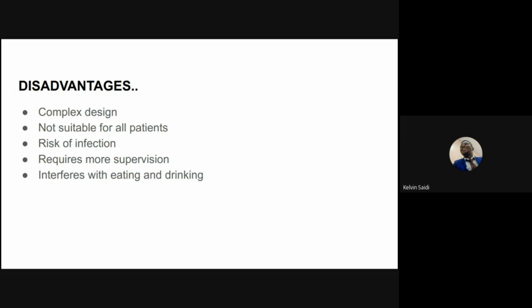It is also important to note that they do require more supervision. So the flow rate of oxygen is adjusted by changing the size of the Venturi adapter. And the amount of oxygen delivered is determined by a specific color-coded adapter. So because the delivery of oxygen is dependent on these settings, it is important for healthcare professionals to closely monitor the patient's respiratory status and adjust the settings as needed.